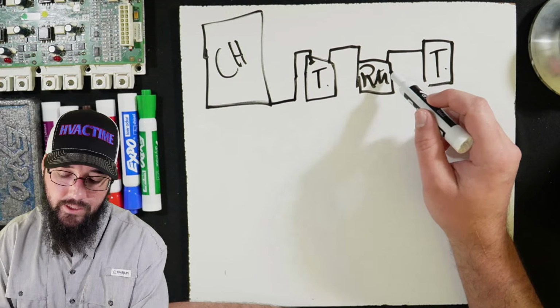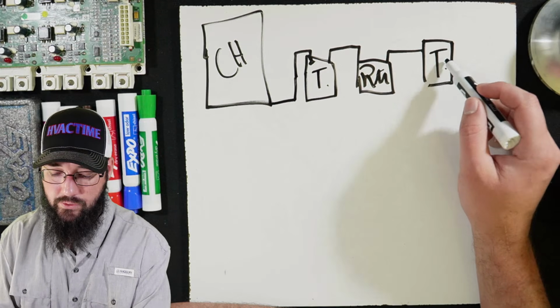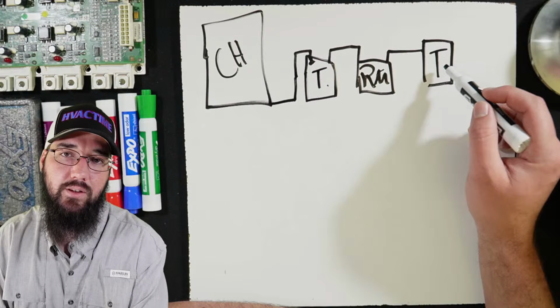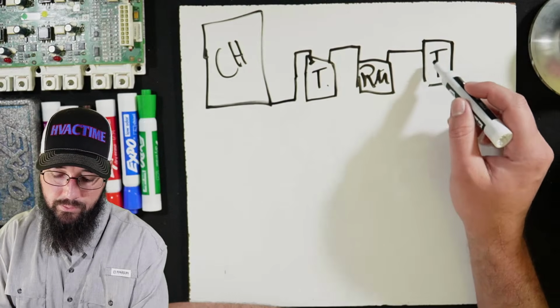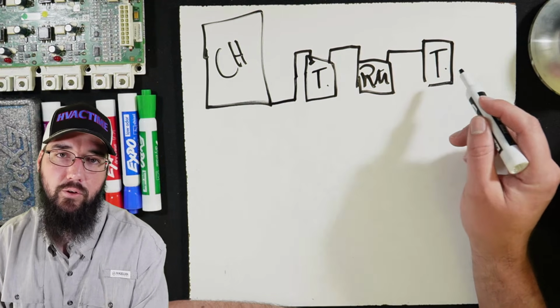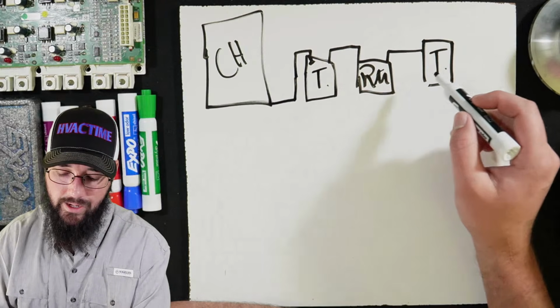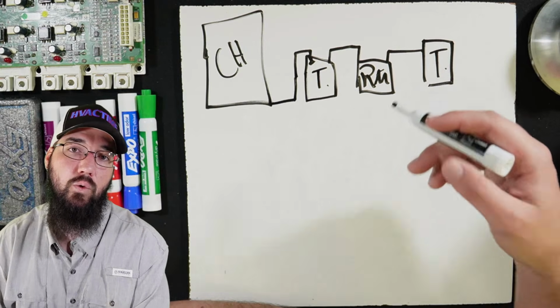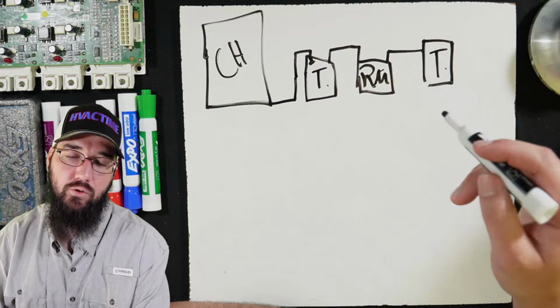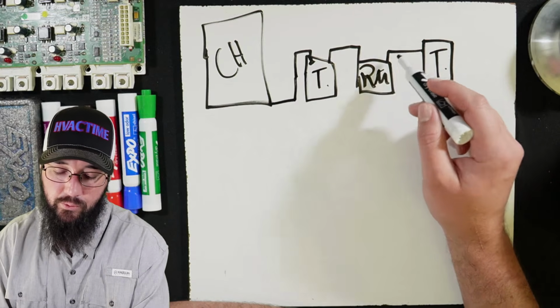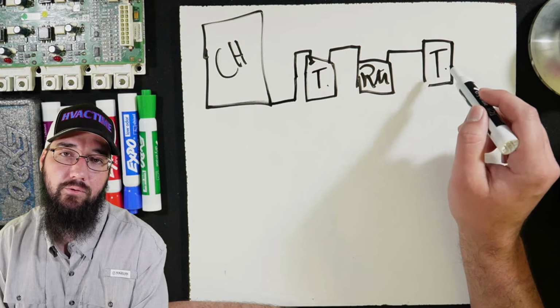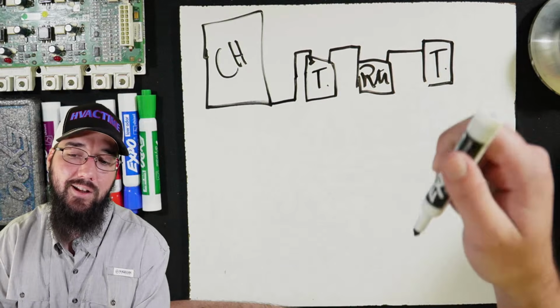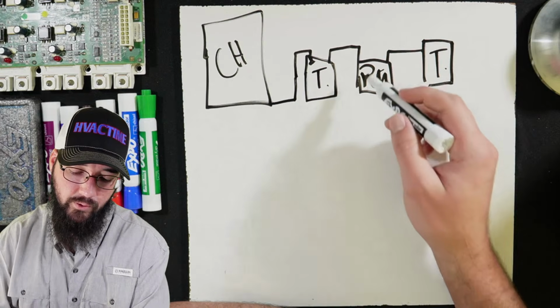But you need to have a subcooler so that you can de-superheat the refrigerant for this tank. Otherwise, as this tank builds pressure, you'll kill your entire process, and you're going to have issues getting this to work effectively. So it's really, really important that a subcooler be used on that vapor tank, which is not true with push-pull.